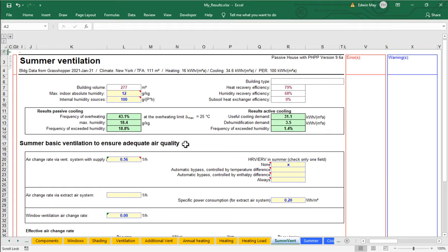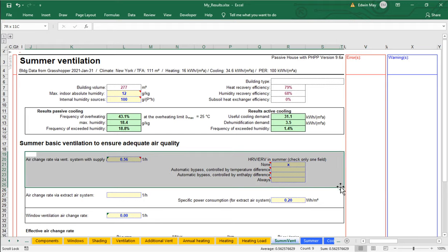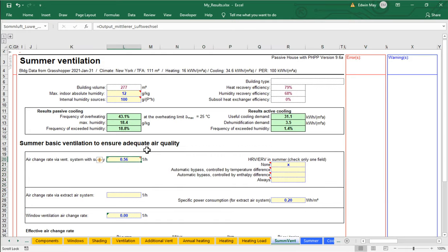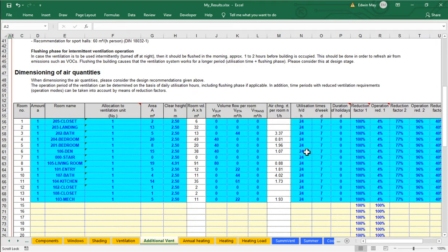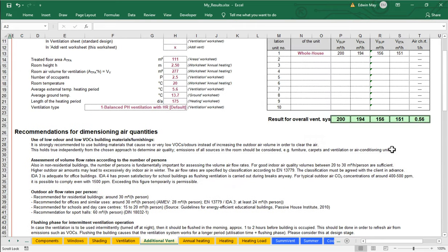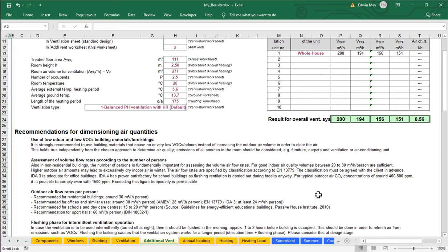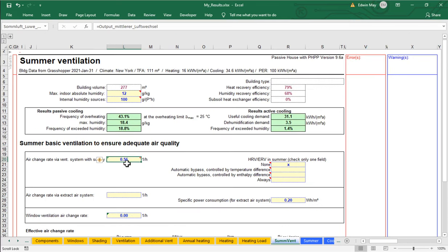Notice that we have some inputs here for a couple of different things. First of all, we have our typical ERV or HRV flow rate. We're going to operate the ERV in the summertime. What is the flow rate that we're going to operate the HRV or ERV at? Right now, we're going to set it to the same flow rate as the wintertime. Go back for a second here to our additional ventilation worksheet. Remember, we input a bunch of information here about our flow rates and about the schedule that our ventilation system operates on. All of that results in a total annual air change rate, 0.56. And currently, in the summertime, notice 0.56, we're using the same information.